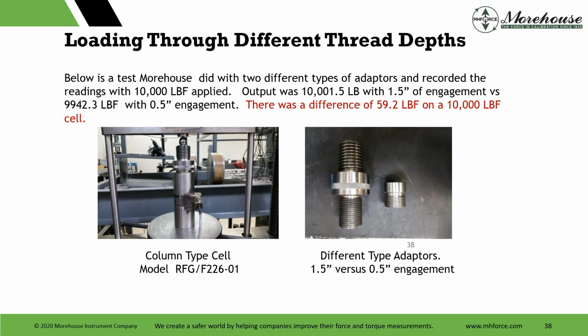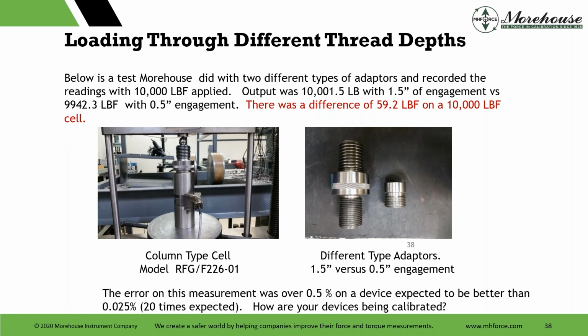This one just had different thread depths. Nothing wrong with this type of load cell. It's a good load cell. The customer just didn't send in their adapters and said, tell me what you did. If we engaged the cell 1.5 inches, the cell read 10,001.5 pounds. And if we engaged it 1/2 inch, it read 9942.3 lbf. So huge difference there. There was a difference of 59.2 pounds on a 10,000 pound load cell. Expected performance was better than 0.025%, is what the customer expected. If they change out adapters, they get 20 times that, about 0.5%.